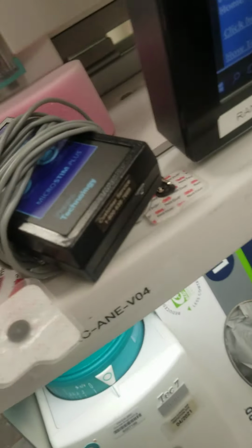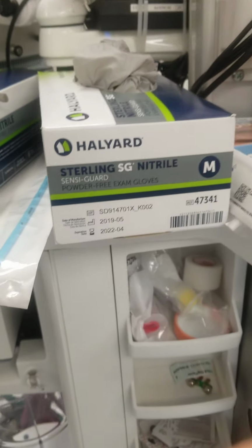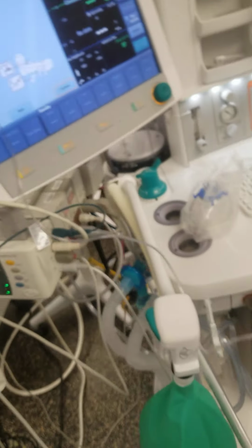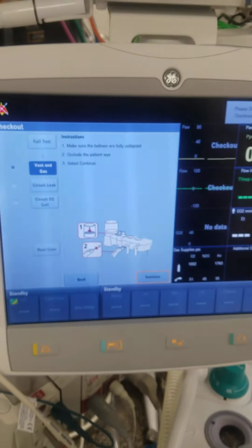It's showing a waveform of a leak. But it's nice to problem solve this ahead of time and not be in the middle of an induction in a case where you're looking at a weird waveform on a capnogram. So if it's going to be attached to the patient, it should be part of the circuit checks in the morning. You shouldn't avoid it, because you'll have a better chance of the circuit checking out with less hardware on there. The whole point is to check if all these little plastic pieces have no cracks in them.